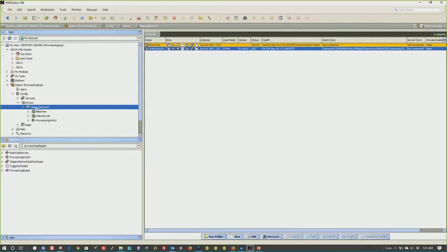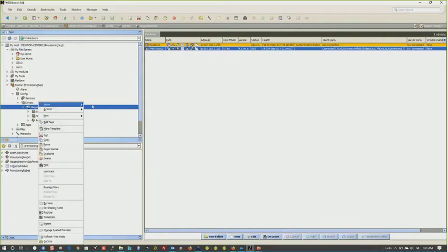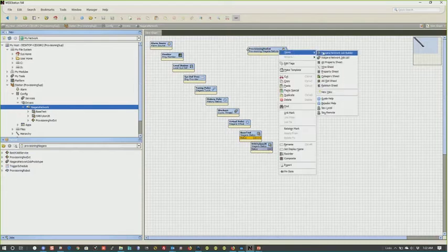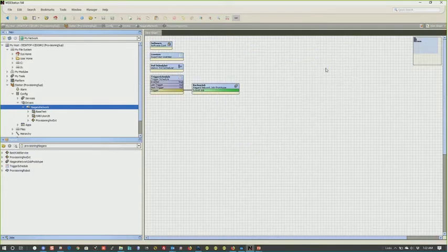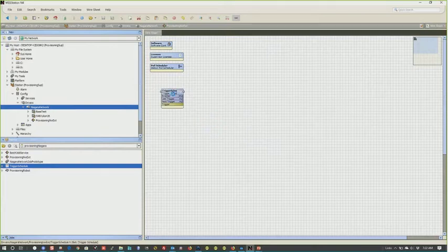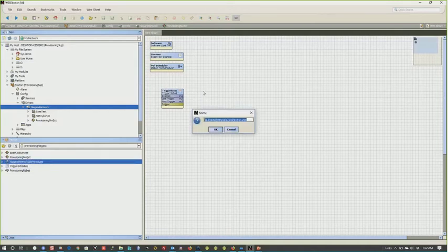Now, if we go in and look at our wire sheet, the standard in there, if you have that provisioning extension we added, if I go to its wire sheet, within here was where I dropped in a trigger schedule and a backup job. So actually, I'll just go ahead and delete them back out and start over. What I want to do is create a schedule so that I back up once a week. You can go in there and set that up. Then you drop in your prototype, and we'll call this JACE backup.